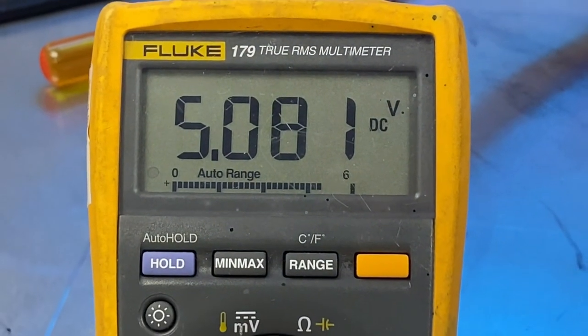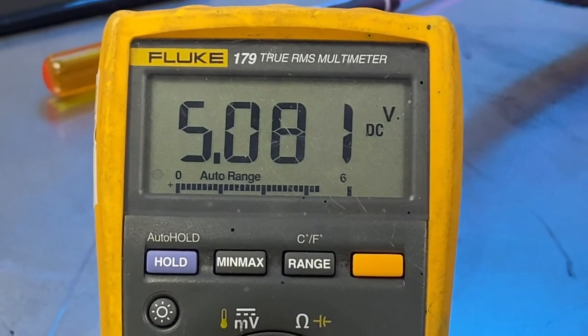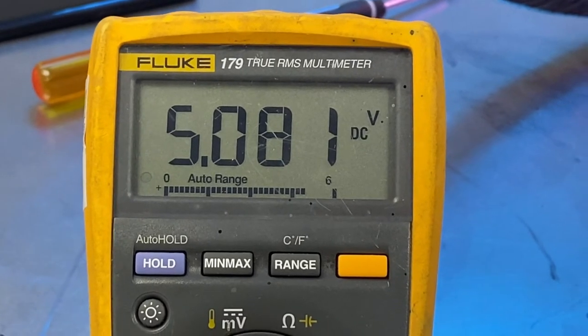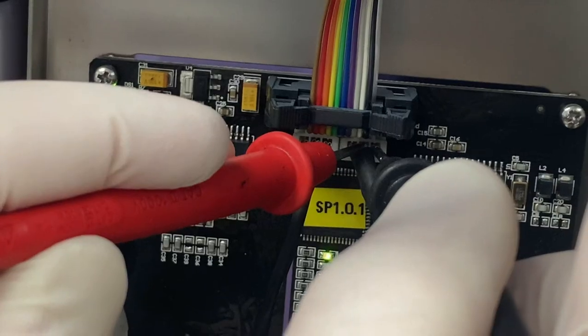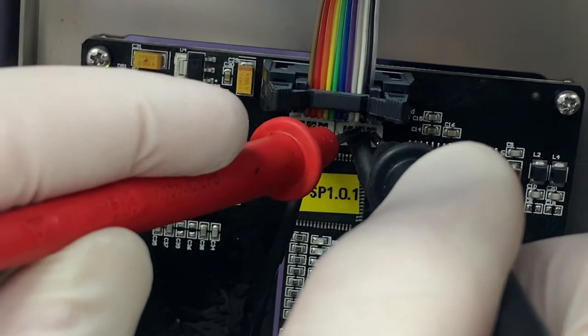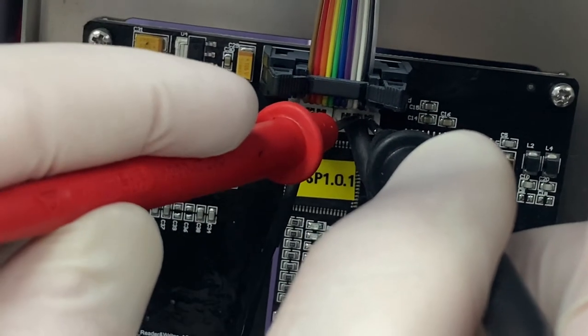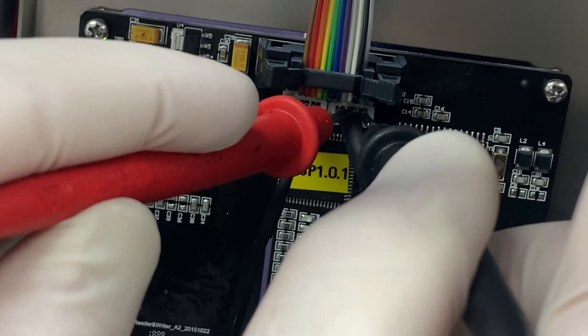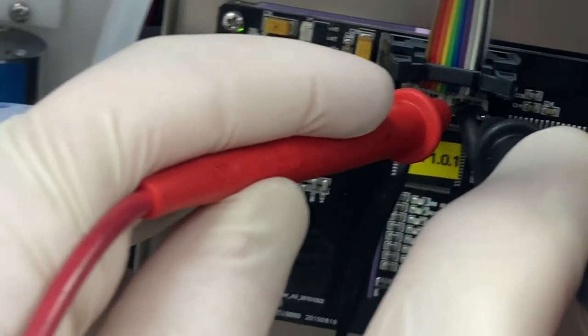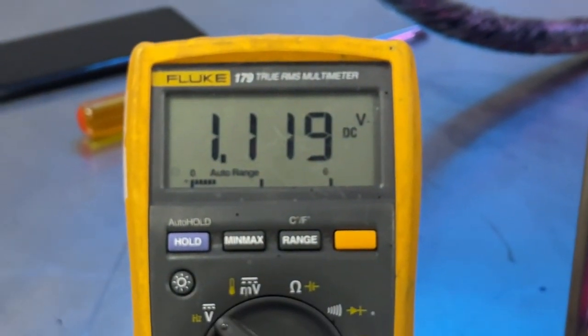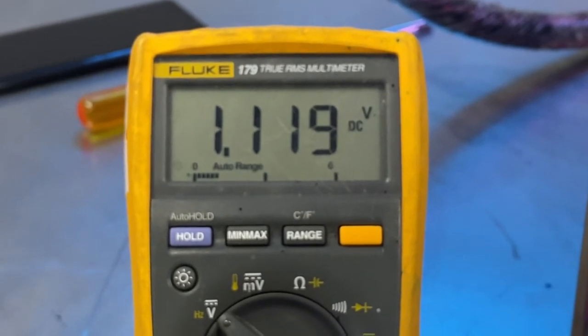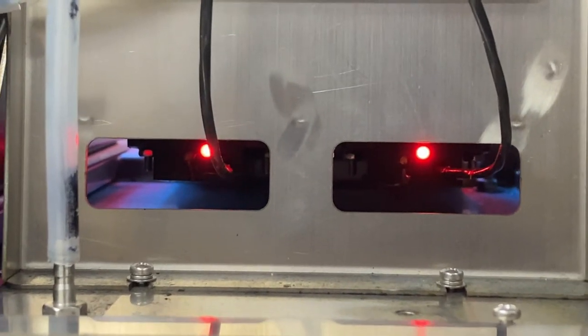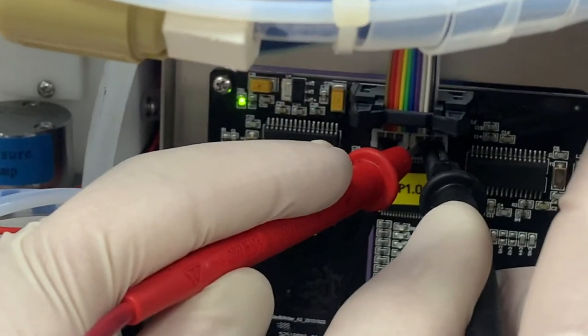So right now we do not have a cartridge installed, or we have an empty cartridge, we're seeing 5 volts for our signal. Okay, I'm still looking at the signal here. We did just slide in a cartridge that does have fluid in it, and now we've dropped down to about 1.1 volts DC, so dropped that signal down quite a bit. So the printer now will recognize that as fluid present, and we should also see that red LED come on the back side of the sensor. So we know that we're getting the proper signals to the machine now.